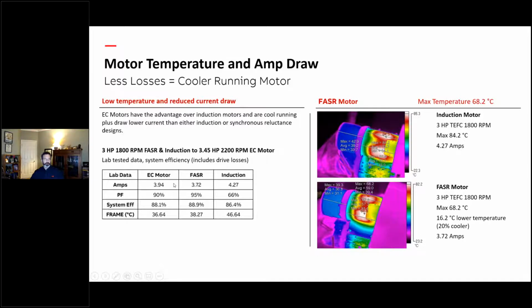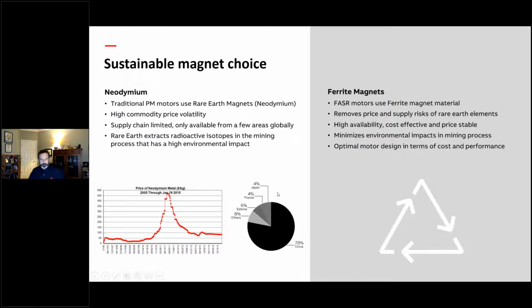EC motors do draw low amps, have good power factor, system efficiency, and temperature. So basically what a FASR motor does is it gets you right in line with electrically commutated motors from an efficiency at full load and speed, performance standpoint, and temperature. One of the things EC motors have touted over induction. I'm not going to spend a lot of time on this because I already talked about that.